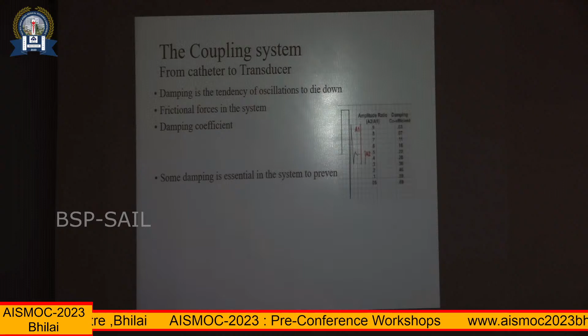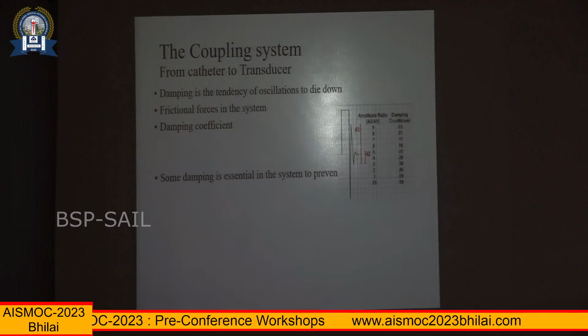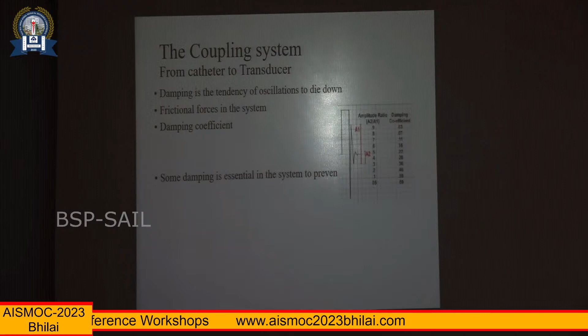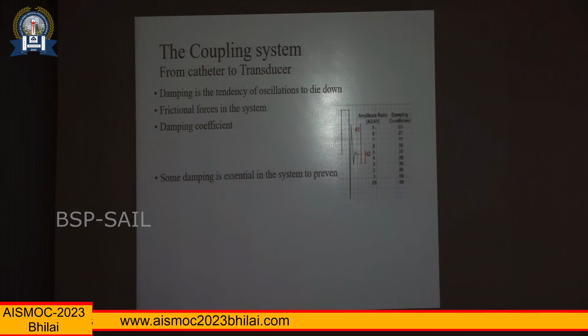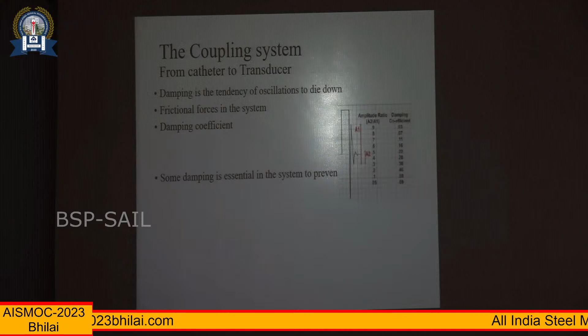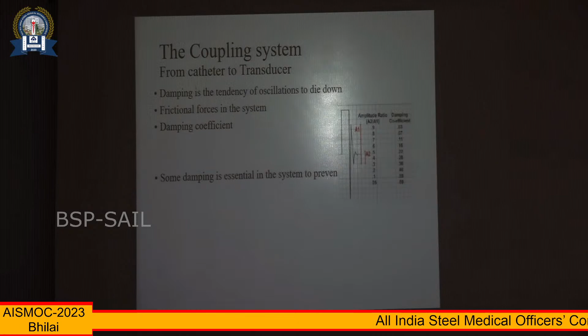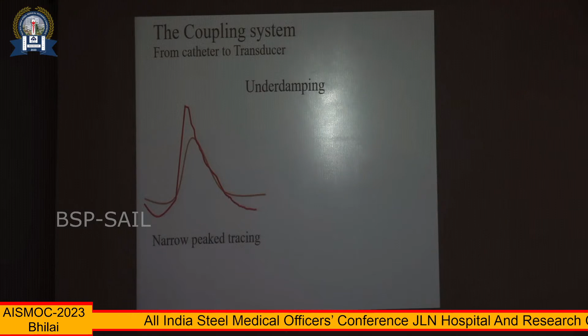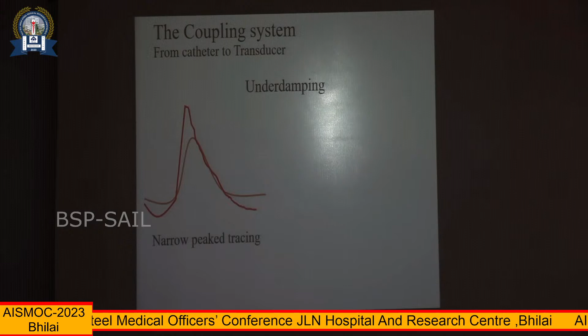So how the system reliably measures, because the system has to be optimally damped. And whether the system is optimally damped, we'll see from the fast flush test. The fast flush test will test the natural frequency and whether there is optimal dampening of the system. Dampening is the tendency of the oscillations to die down, because otherwise the system will keep oscillating and you don't want the oscillations to continue. If you see a trace that is flatter, we say it is an over-damped system. If you see a trace which is very spiking and very resonant, you can understand that the system is under-damped.